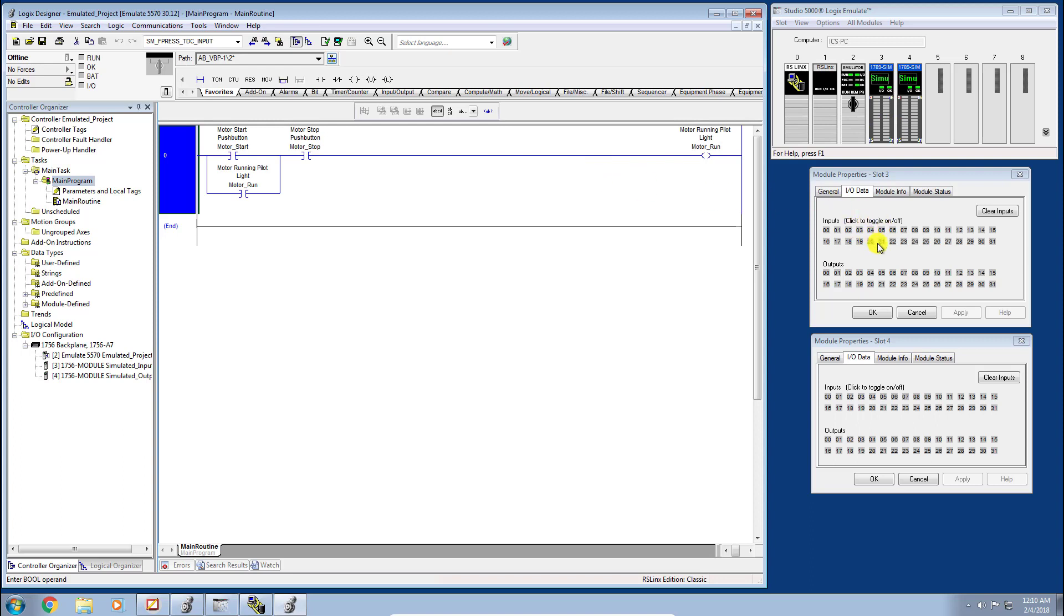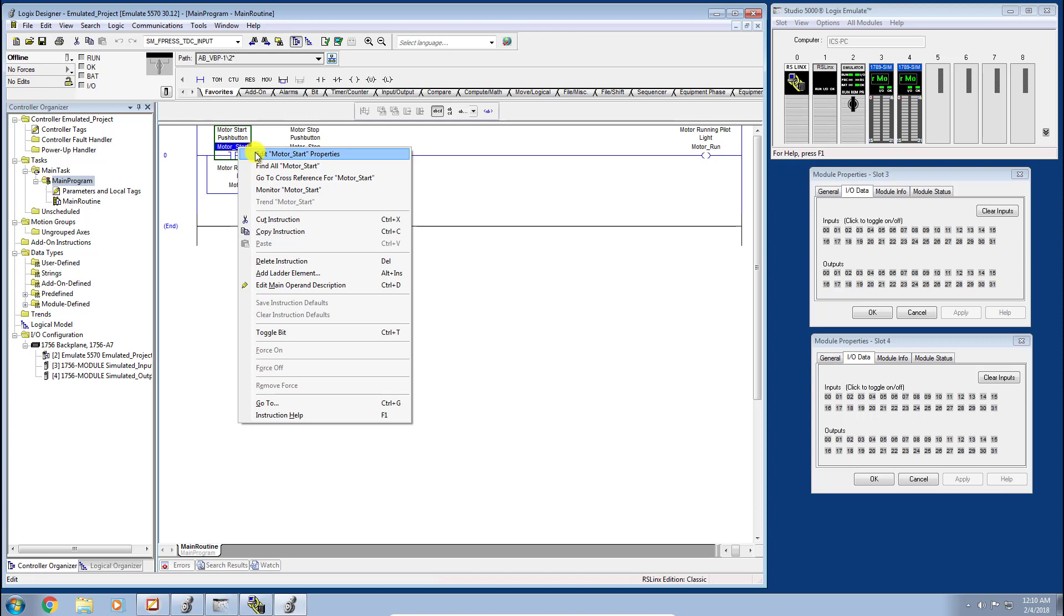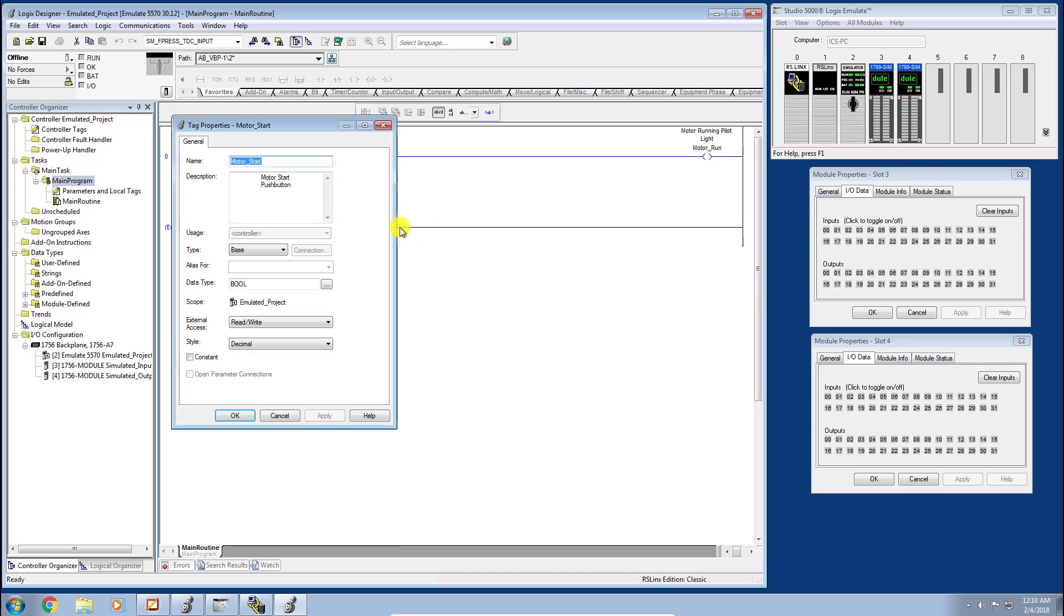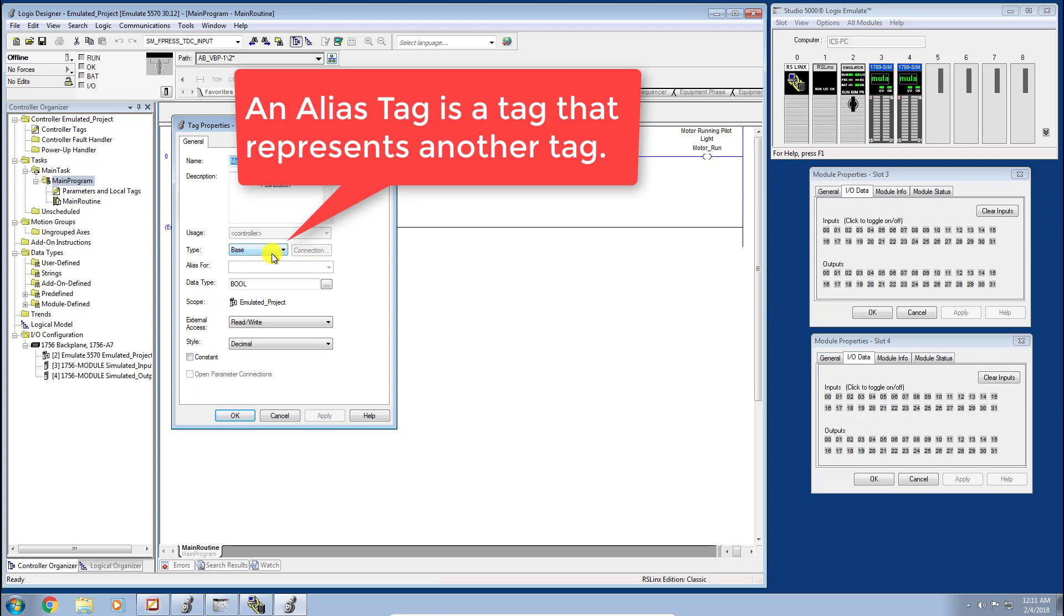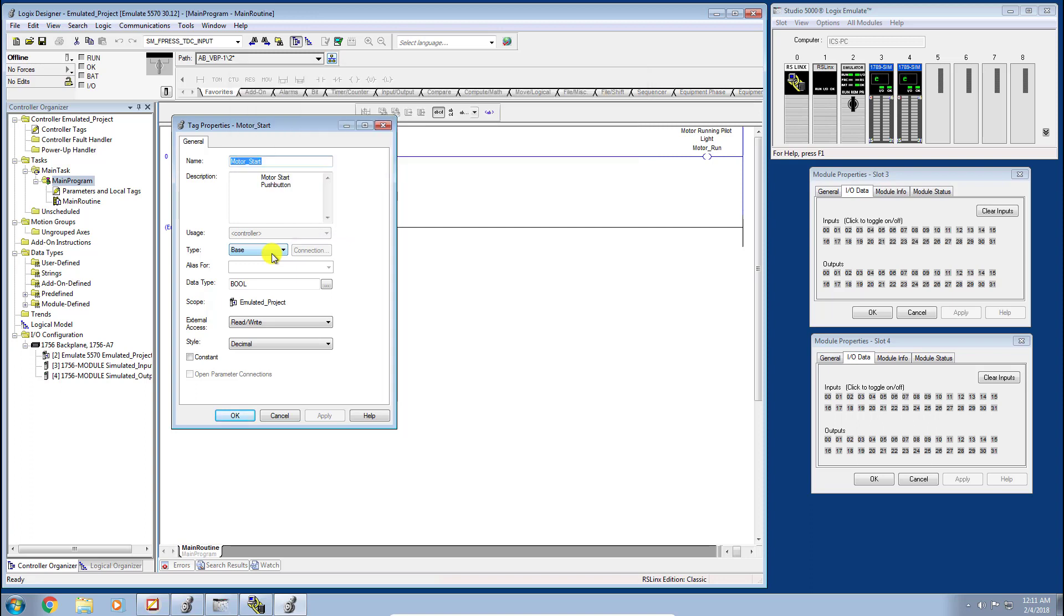To do that, we need to go in and edit the existing tags we created. I'm going to do that by right-clicking the tag name and going to Edit Properties to create an alias tag. What we need to do is change the type. And what is an alias tag before we even do that? An alias tag is a tag that represents another tag. You can think of it as a pointer if any of you have any programming or C experience. It's a pointer to another location in memory, and that location that we're going to point to is a simulated or physical input or output point.